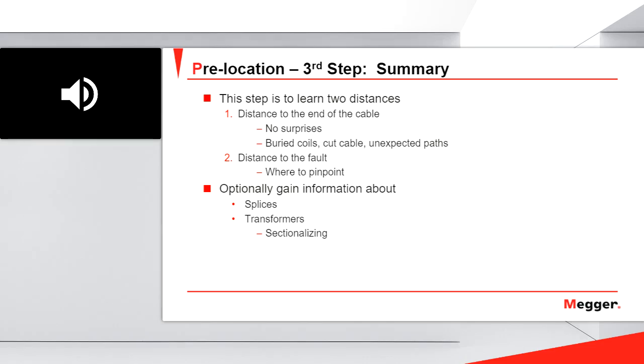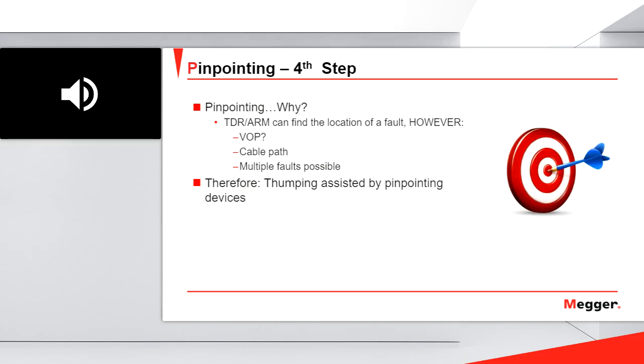Once I am done with the third step, I need to do the last one, which is the pinpointing. The reason I always need to pinpoint the fault is that the cable doesn't run straight. We can have coils, maybe the cable goes down, then up, we have some curves. So we have different situations. For that reason, after I have prelocated my fault, it is always good to pinpoint the fault. So that is what I will do.